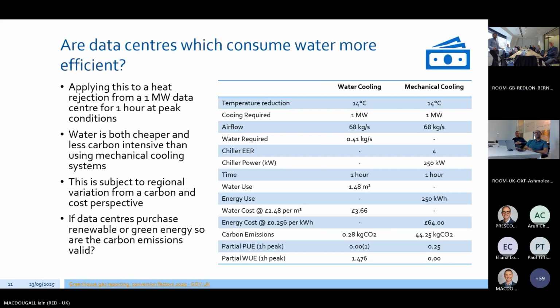So where does that take us? If we need 14, let's say we need just 14. Keep it nice and simple. We want 14 degrees C of cooling. We can either use it with water, or as an equivalent, mechanical cooling. So with water, and let's say we want 1 megawatt of cooling, just to keep numbers nice and simple. The airflow is the same in terms of if you're delivering airflow through your heat rejection plant, you're still rejecting that same amount of heat. So you need 0.41 kilograms a second of water to reject that heat. So that's the airflow times that moisture content per kilogram of air that we looked at earlier.